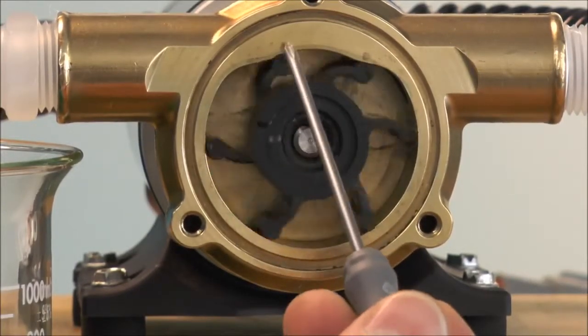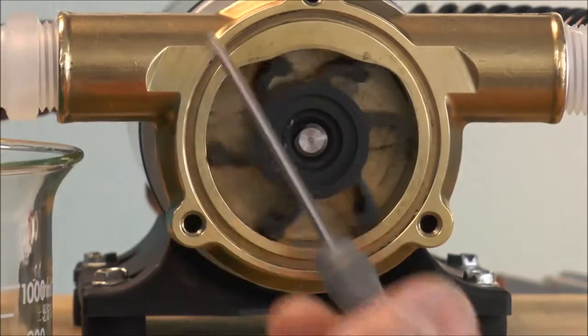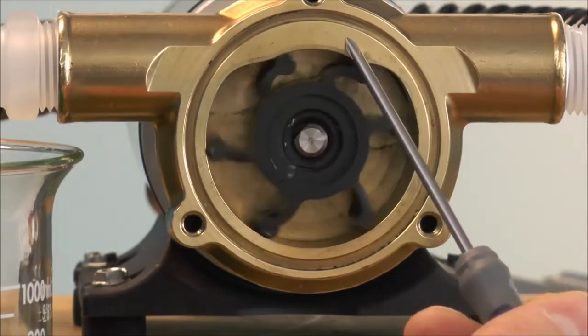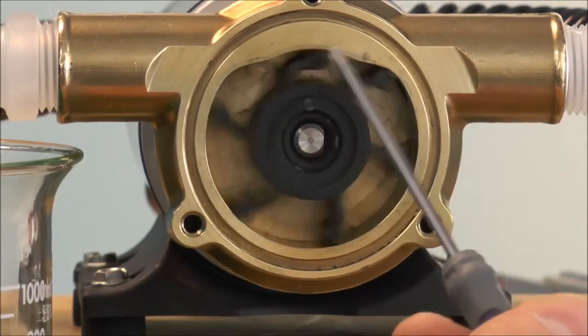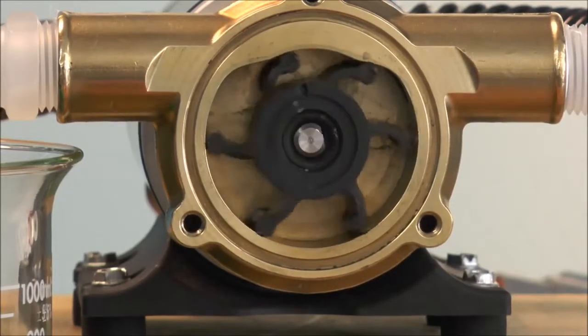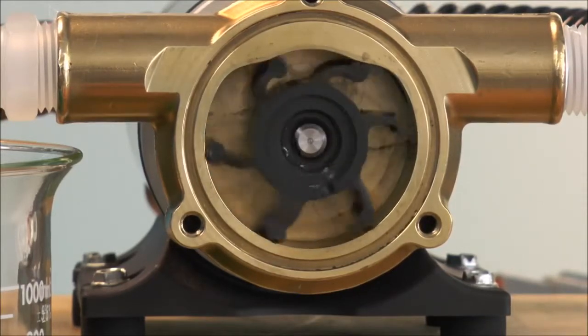What that does is once the vanes come on this side it creates a negative pressure which draws the fluid up into the impeller cavity down and around. And again that cam squeezing those vanes, folding them over, pushing the fluid out to discharge. What we're going to do is we're going to put a clear end cover on and give you a better idea of what's going on inside the impeller pump.